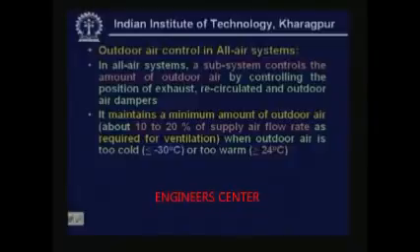When the outdoor air is very cold, say less than minus 30 degrees centigrade, or when it is too warm, say greater than about 24 degrees centigrade, then the subsystem supplies a minimum amount of outdoor air to the conditioned space. This minimum amount will be about 10 to 20 percent depending upon the application, and this minimum amount is required for ventilation. So this is maintained as long as the outdoor air temperature is too cold or too warm.